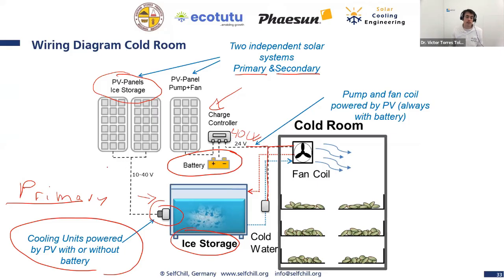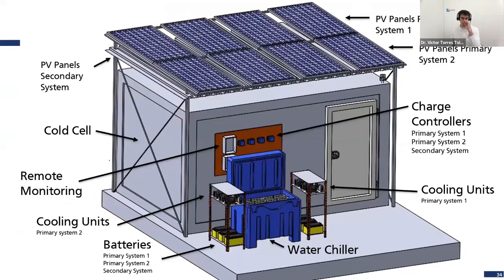And in the primary system, we are dealing with much more power, so more or less 550 watts for 6 cooling units. So the primary system is always bigger, of course, to generate the cooling energy. Let's have a look at this diagram and try to find all the components there. Let us start with the primary systems. So we see here PV panels of the primary system. We have 3 cooling units with the first primary system. These 3 PV panels are providing energy through one charge controller to these 3 cooling units, right?